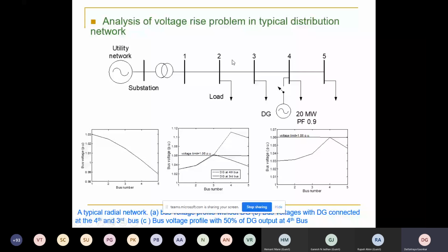When there is no generation, you can see voltage keeps dropping. Another important thing is, because voltage goes low at the last customer, the operator thinks: why not keep the voltage a little higher here so this person gets proper voltage? He knows it will drop, so to compensate, he keeps the voltage at this point higher, but within limits. So you see it's not 11 kV, it's higher than that—he raises the voltage level and lets it drop. If it were lower, imagine the voltage at the last customer. So that's the situation without generation.